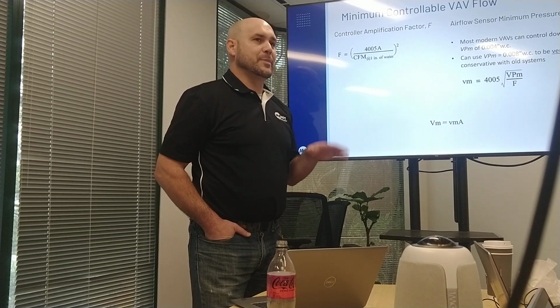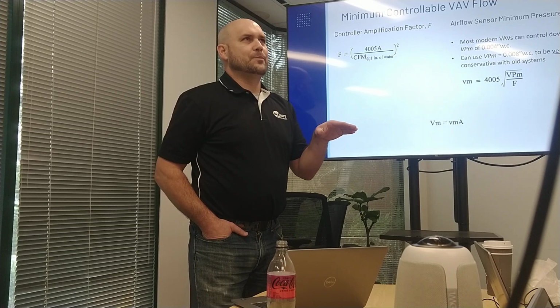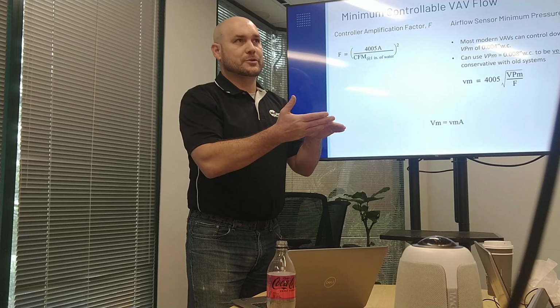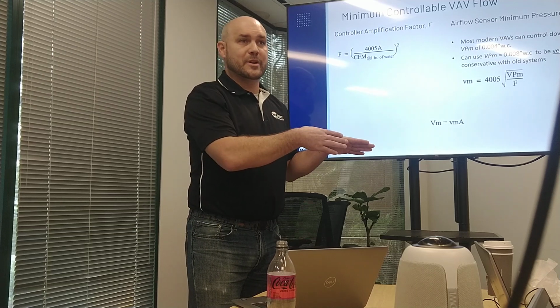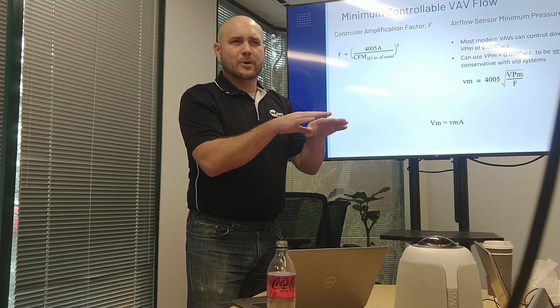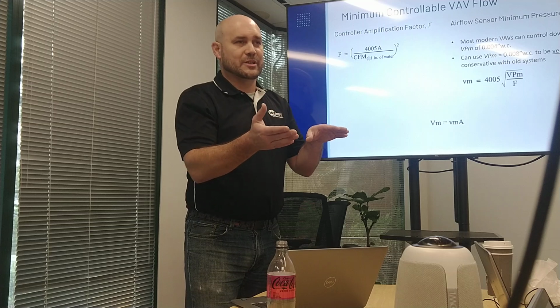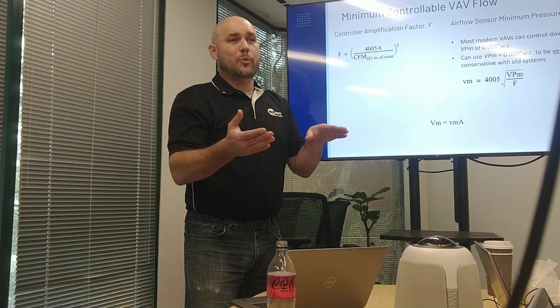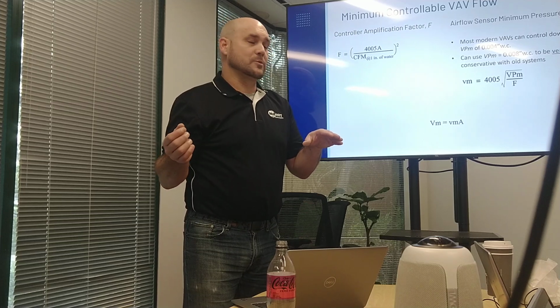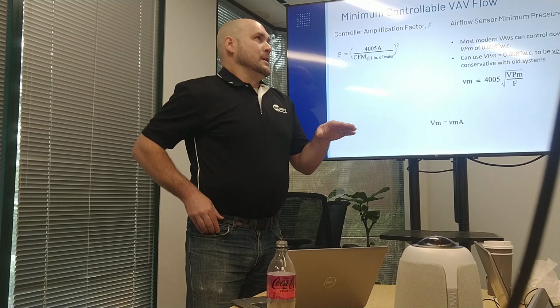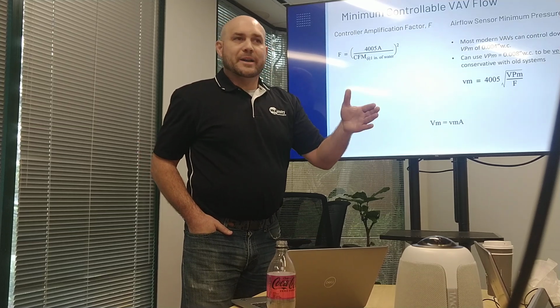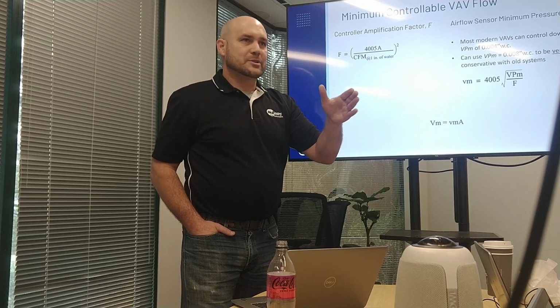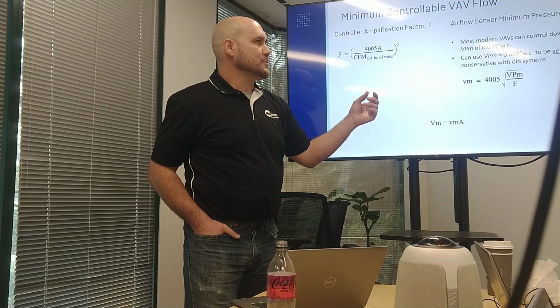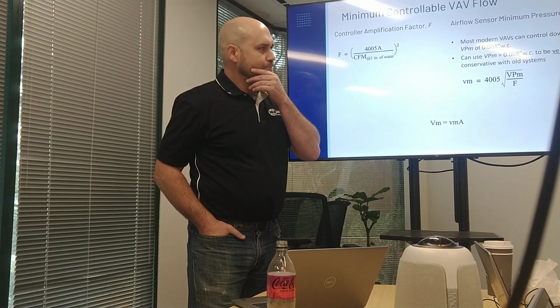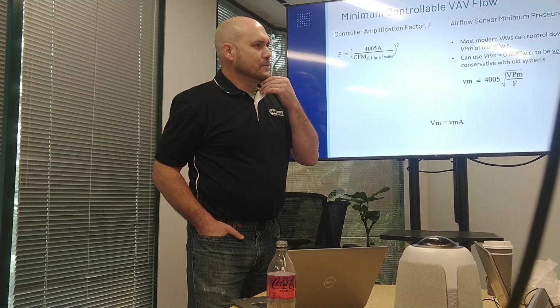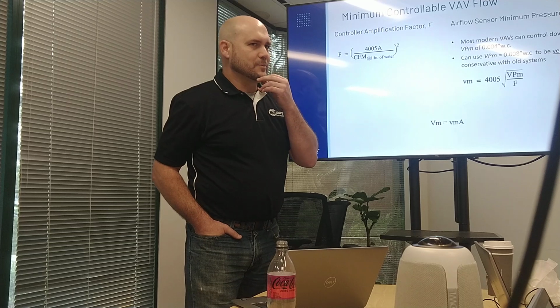Largely they're unrelated. I would say that the box minimum is going to provide a floor. Ultimately, it's going to provide a floor for what your air handler minimum would be, and it's not exactly 1-to-1. But you can't have an air handler minimum, like you said, of 0. You probably can't have an air handler minimum of like 0.2 either, depending on where that's measured in the ductwork. But this is at the boxes with the damper wide open. And once your damper starts closing, that's still the minimum sensitivity of the sensor. They're correlated, but they're not directly related, I guess would probably be the short answer.